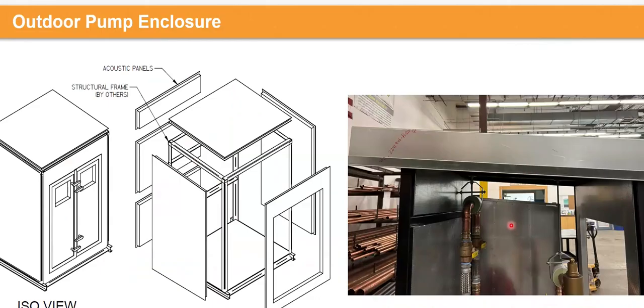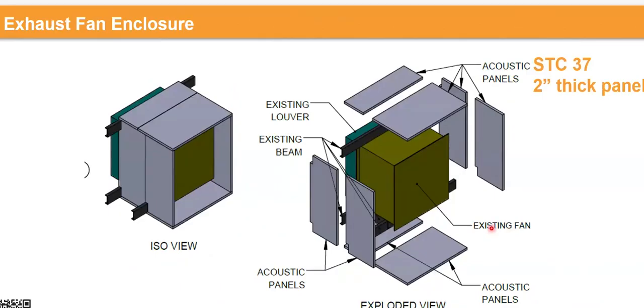We did have another job where there was an ice rink where kids would play, and they had an exhaust fan that was pulling a lot of air out of that. This was getting very noisy, and I believe they were around 60 dBA for this particular space. What they needed to do was come down to 50 dBA, which would be exactly where they wanted to be for these kids. We did run our acoustic analysis because we do have the software. We figured out that most of their issues were from the radiated noise. So we provided 2-inch thick panels, STC 37.